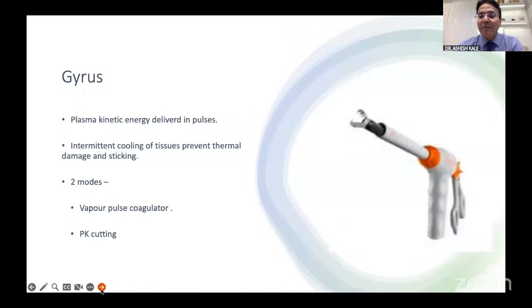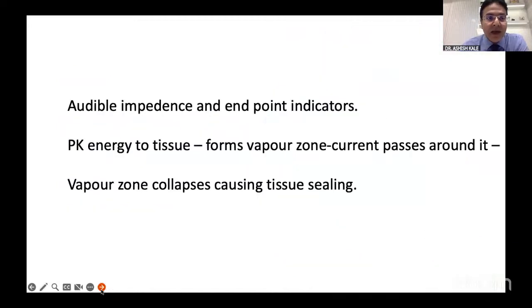Coming down to the bipolar Gyrus, it uses plasma kinetic energy, which is delivered intermittently. There is cooling of the tissue to prevent thermal damage, and there is less sticking. It acts on two principles: first, a vapor pulse coagulator, and second, plasma kinetic cutting. The audible impedance is the endpoint indicator.